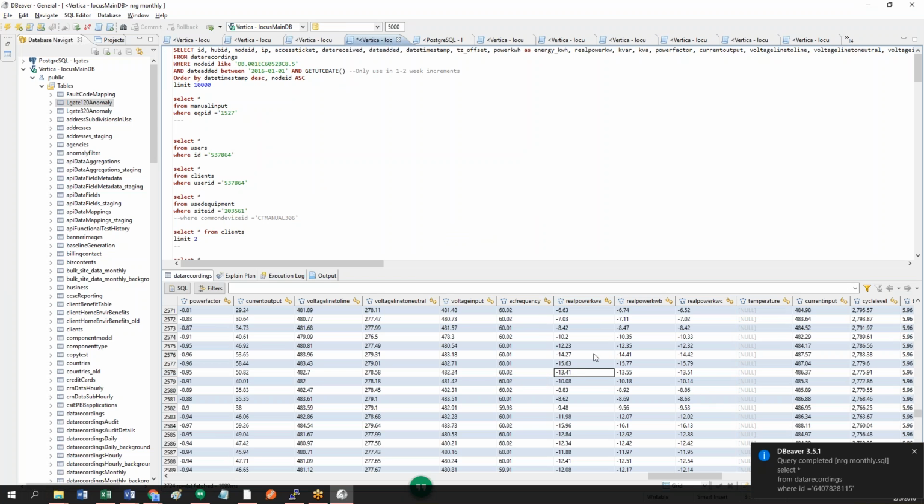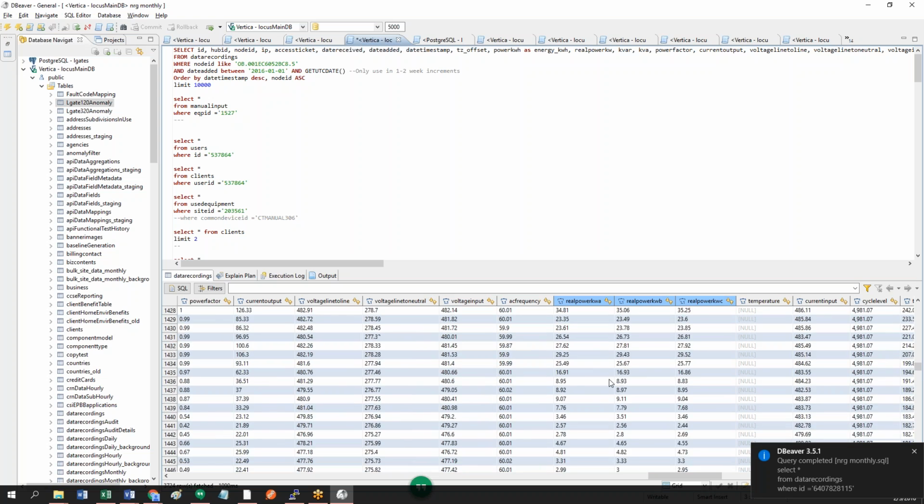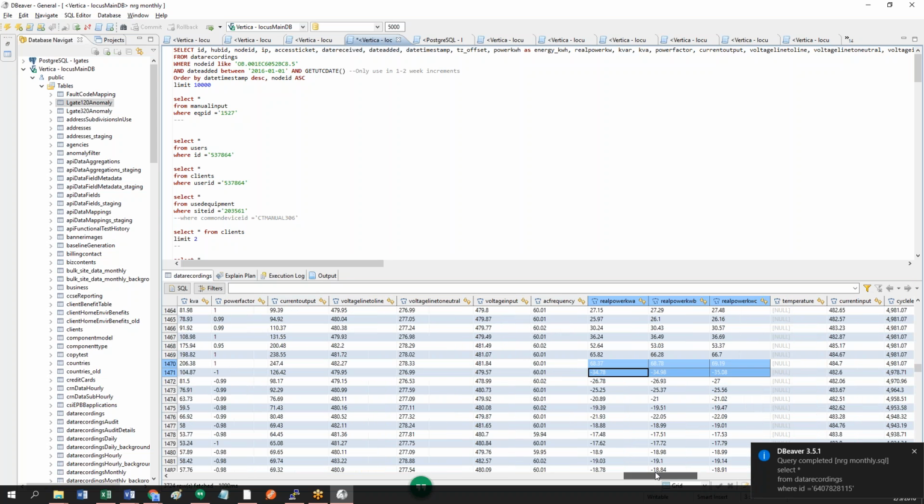I do a slightly different one. Here, same thing, right? You've got all 3 that they're all basically balanced, but they're all reading negative. So you can tell the guy, hey, flip them on site, and he flipped them. So quickly after you make that change, you can see right here, right? 1 second they're negative, and the next second they're positive. And that's within that 5-minute period. And you can tell here as well, under power factor. So it went from -1 to 1.